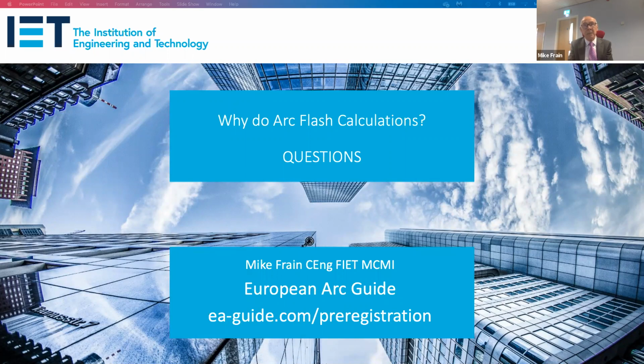So the amount of energy let through in those circumstances can be enormous, and quite often that's the case. A lot of the high incident energy levels I come across in industry are on LV equipment that hasn't been maintained properly, where we've had to look at 2-second disconnection times, and as a result the incident energy downstream has been quite high. So impedance is vital - it can be your enemy as well as your friend. If you've got low impedance, even with very high fault levels, particularly for HRC fuses that I've described, they can disconnect a dangerous fault very quickly, providing the impedance is low enough to allow enough current to safely rupture that fuse or disconnect that circuit breaker.